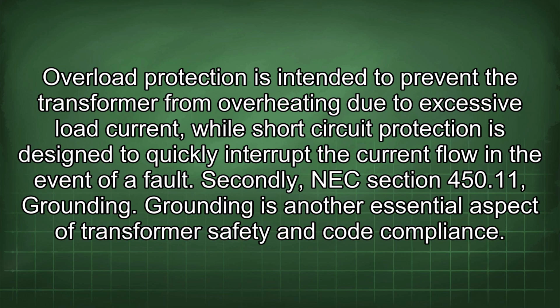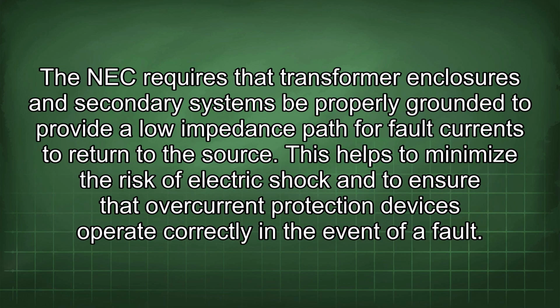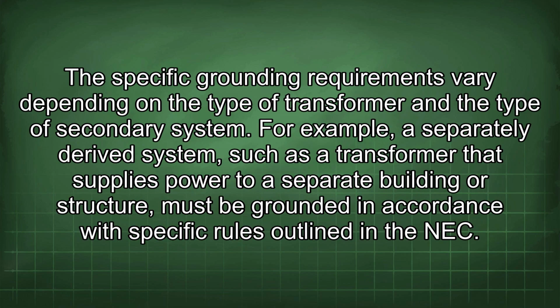Secondly, NEC section 450.11, grounding. Grounding is another essential aspect of transformer safety and code compliance. The NEC requires that transformer enclosures and secondary systems be properly grounded to provide a low impedance path for fault currents to return to the source. This helps to minimize the risk of electric shock and to ensure that overcurrent protection devices operate correctly in the event of a fault.